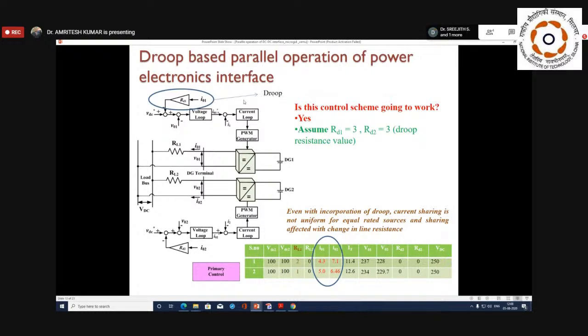Okay, so here I have incorporated one droop. So what is there? I01, that is the output current of the converter 1, is going to be multiplied by the droop resistance. So basically I01 into RD is going to be a voltage. Okay, and this is going to be subtracted from the common DC link voltage. So what is the common DC link voltage?